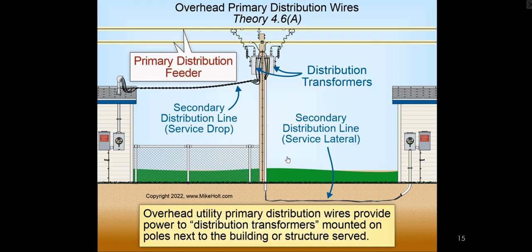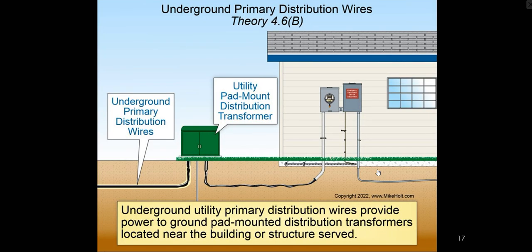On the other side here, you have what are called service laterals, and that is the lines when they're run underground over and again to the meter base through the disconnecting means and into the structure. So, underground utility primary distribution wires provide power to ground pad-mounted distribution transformers located near the building or structure served. It also could be what's called a handhole or a splice box. And those boxes are basically a large fiberglass box, oftentimes, that allows conductors or even pipes to come up inside of it, and there are splices right there, and then it goes out to the building. It isn't always a transformer.